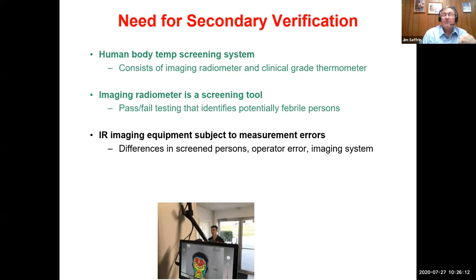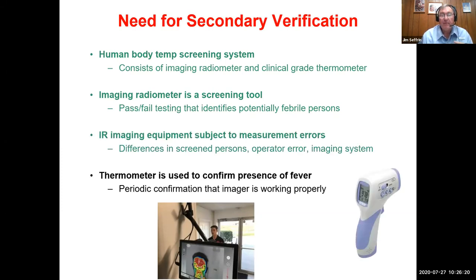Be aware that infrared imaging equipment is subject to measurement errors due to differences in screened persons, operator error, or within the imaging system itself. When you have someone that indicates a positive result with the thermal imager, we then use a secondary tool. In this case, pictured here, we see a medical grade infrared thermometer to confirm the presence of a fever. We can also use this if we are operating a screening checkpoint at the entrance to a school or facility. We can also use that thermometer for periodic confirmation that the imager is working properly. So if persons are passing through and you're getting a reading of 98, 97, 97.5, and your independent confirming thermometer is confirming those numbers, then you have agreement and it confirms that you're doing things properly.